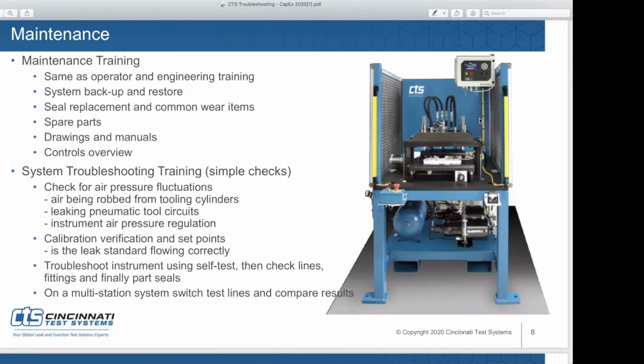The other thing is use the instrument self-test caps. Start with the instrument, check to make sure it's not in the instrument, and then work your way out. Test lines, cap a test line before it goes into tooling. Make sure there are no fittings or valves leaking in the test line. And then go to your tooling and work through every one of the seals like we talked about earlier. Are they burping? Are they actually leaking all the time? Are they wearing?